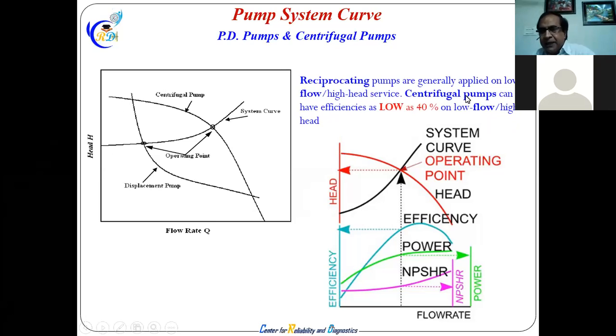Okay, so reciprocating pumps are very low flow, but high head, high pressure. You can see it like this. So these are called system curves. System curves look into frictional loss and dynamic loss. Frictional loss means dynamic loss and static loss. These two parts combined give the system curve.